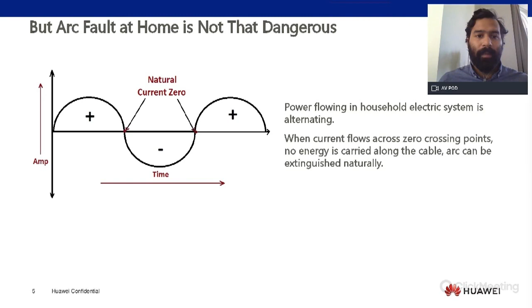So now, arc faults on PV systems. In PV systems, we have a DC side on the modules. After the inverter, we will have the AC part of the installation. Now on the DC side, if there is an arc fault, this is considered more hazardous because this will not be extinguished naturally, like in the case of AC.